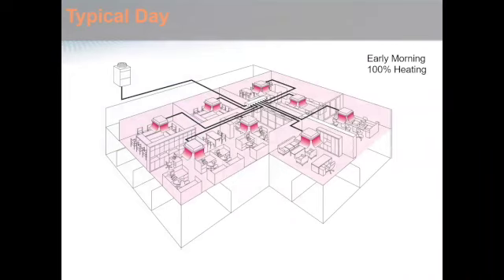So now we're just going to touch on a typical day, and this is going to be showing you the value of the heat recovery system as we discussed earlier. So let's consider this a typical fall day. This is building startup, early in the morning. We're going to be in 100% heating mode. We're really going to be trying to heat that space up to an acceptable temperature for everyone to come in and start working. So this application is going to be 100% heating early in the morning.